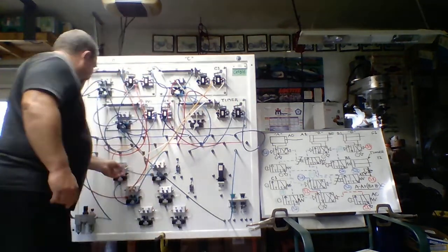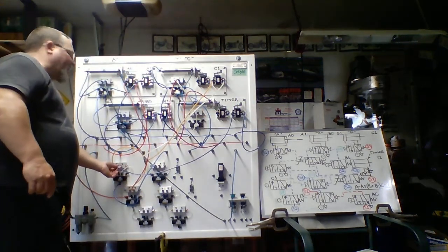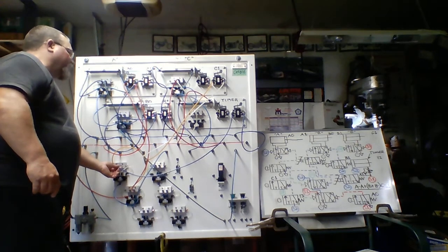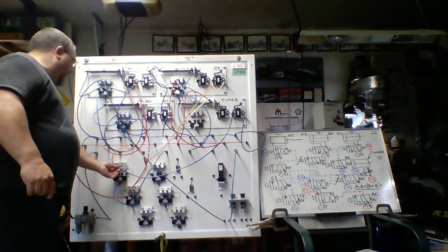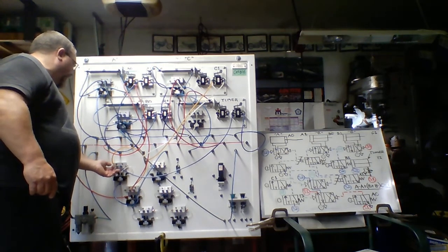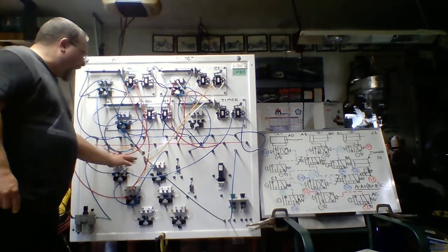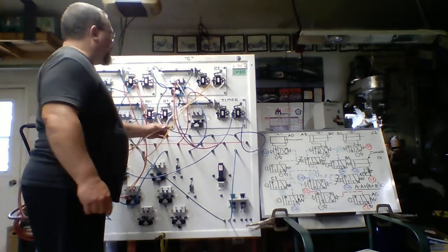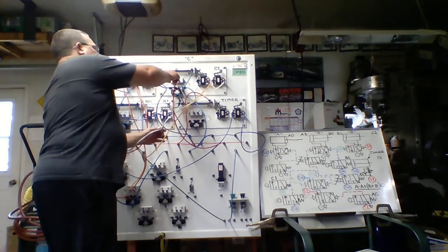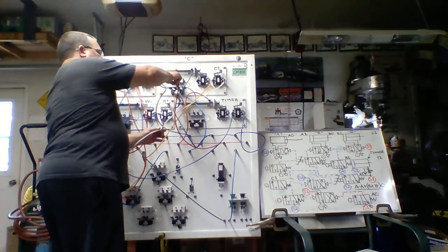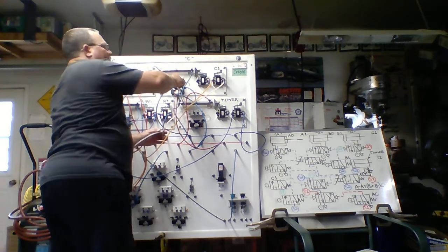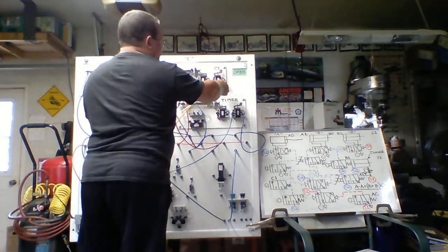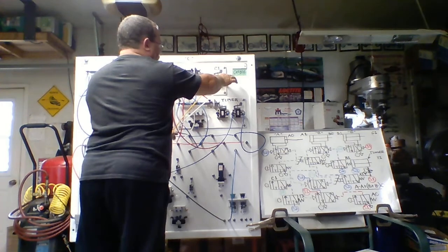We look here, and it's going to pilot the second cascade valve to shift so that now we open the path for source 3. And at this point in time, we have source 3. We look here, you can see where it's teed off. So the first thing that's going to happen here for source 3, it's going to get C to extend, as indicated here at the pilot. C extends, it gets on C1. We supply C1 with source 3.